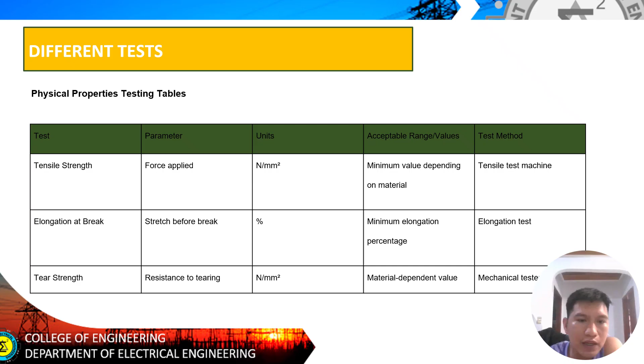So these are the different physical properties tests for cables. Tensile strength, the force applied, all of that is checked, with minimum value depending on material and test method in tensile test machines. Elongation at break is the stretch before break, in percent, with a minimum elongation percentage, tested using the elongation test. Tear strength is the resistance to tearing, a material-dependent value tested using mechanical test. Those are the different tests under physical properties testing for cables.